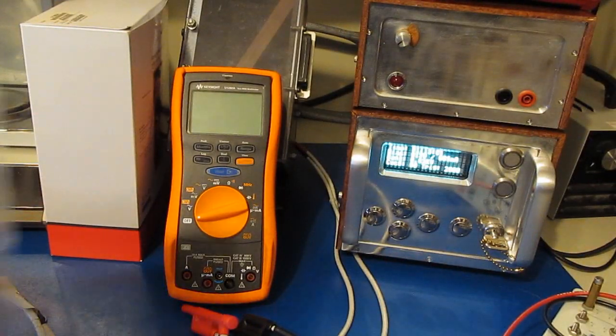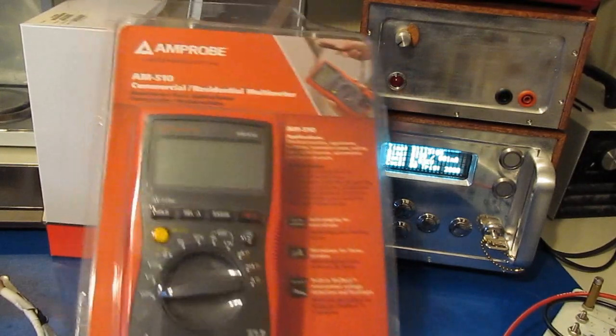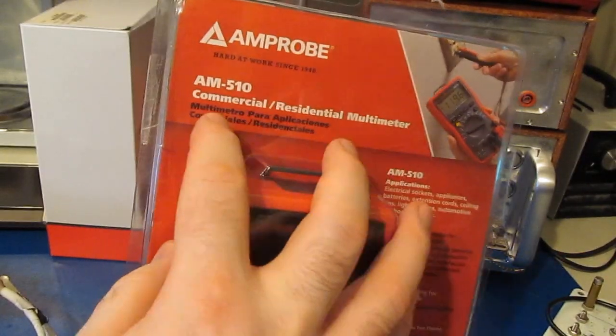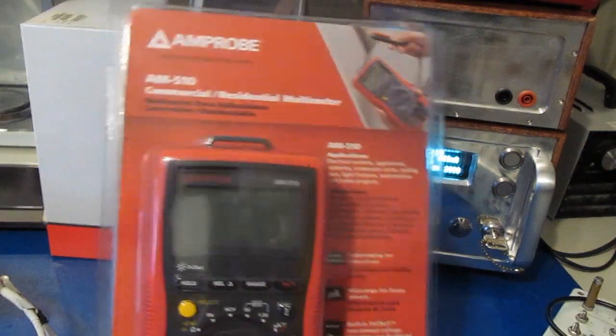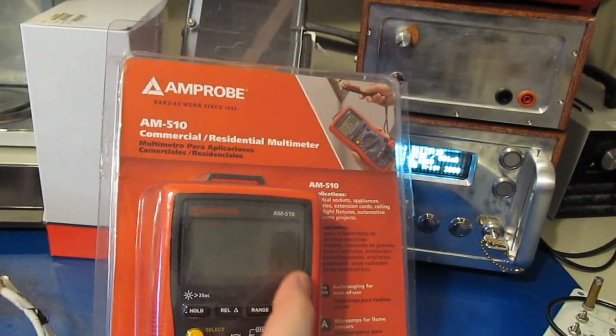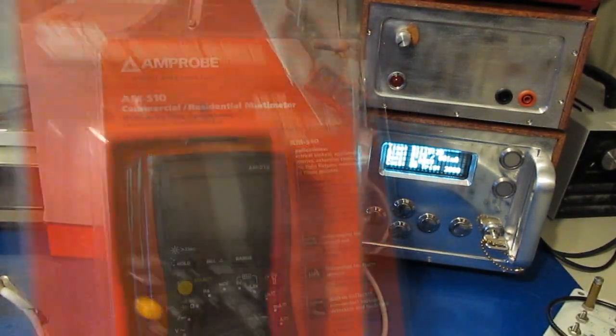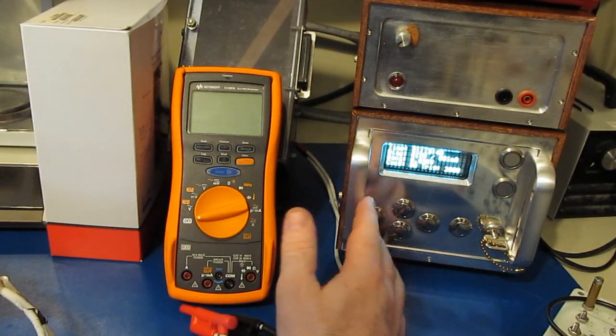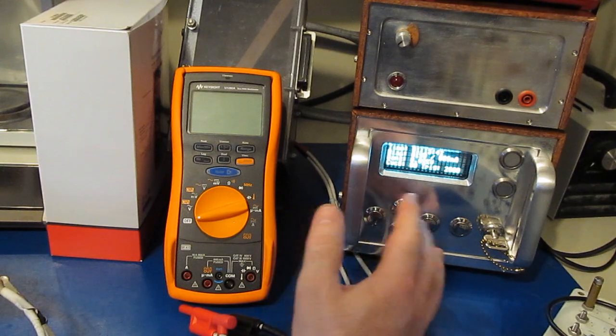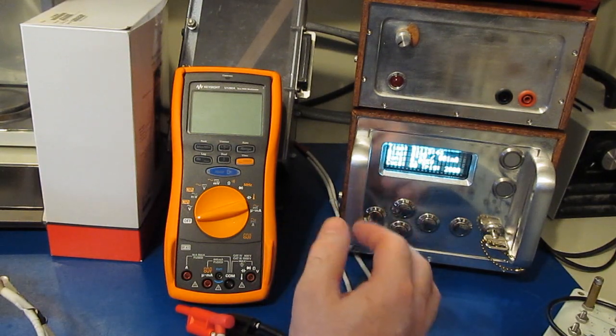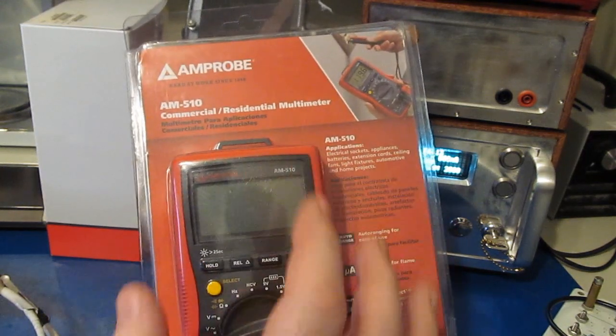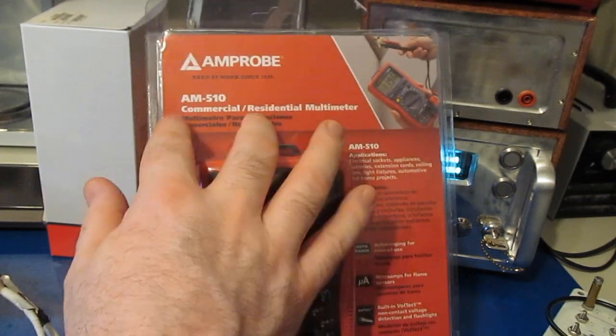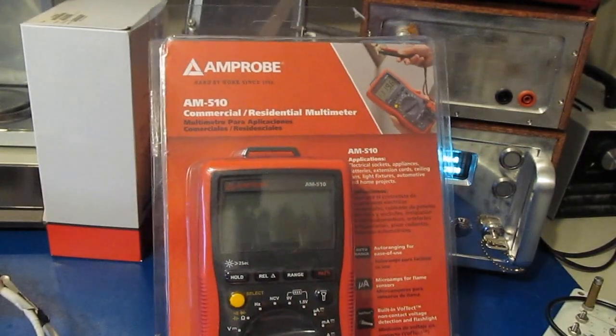Again, I had started these tests running some $50 meters. This particular meter right here, the Amprobe AM510, was the runner-up of that very first test I ran, and this meter was damaged at 5.8 kilovolts. I used that criteria to set the limits of this generator, so this transient generator can go up to just shy of 6 kilovolts peak. When I'm talking about meters that are electrically robust, I'm referring to meters that exceed what this Amprobe AM510 did with our original testing.